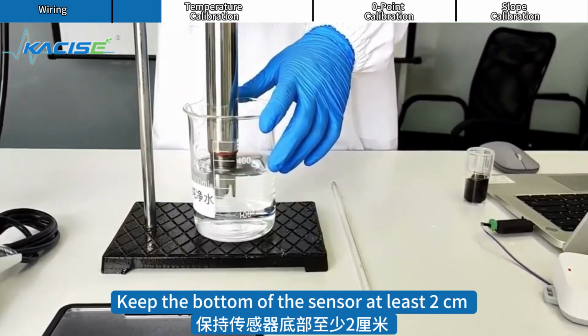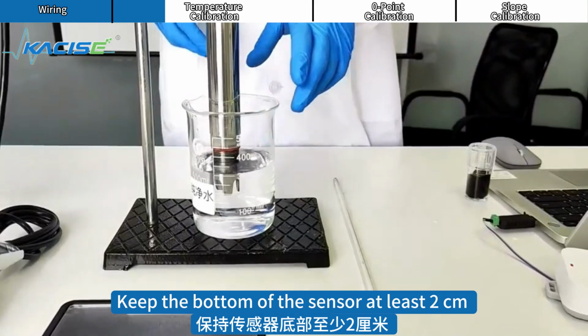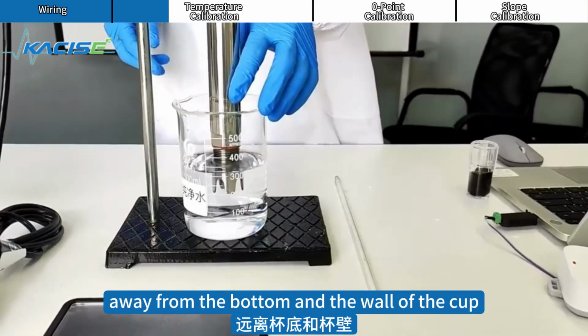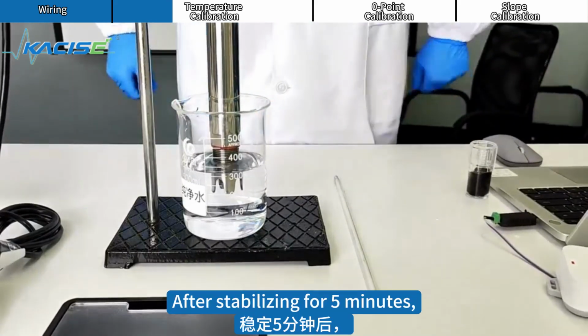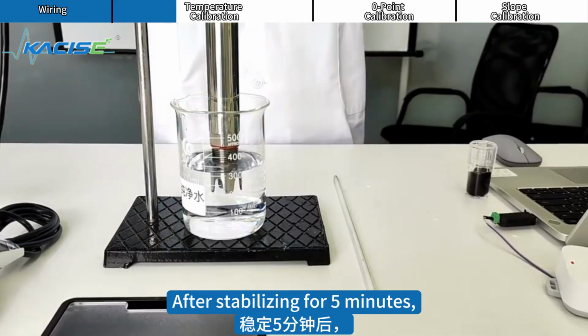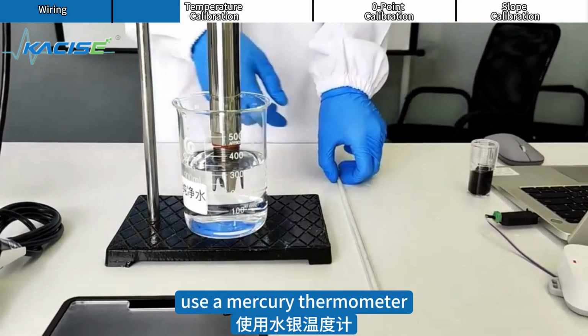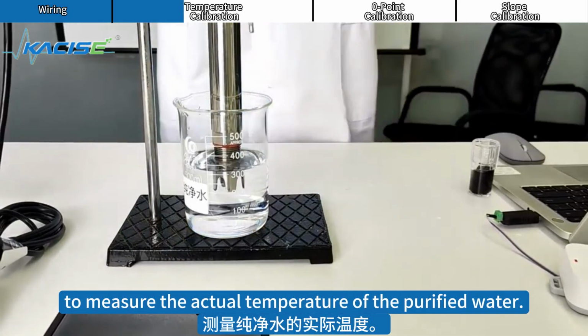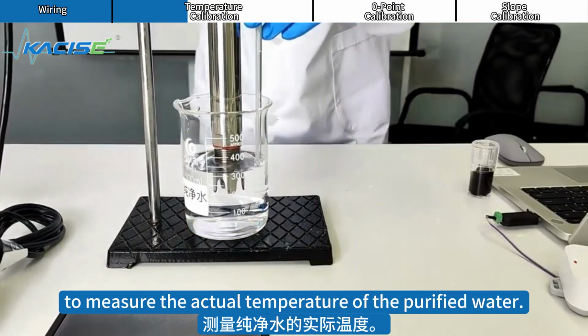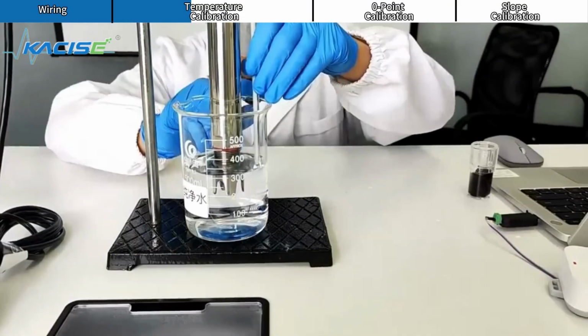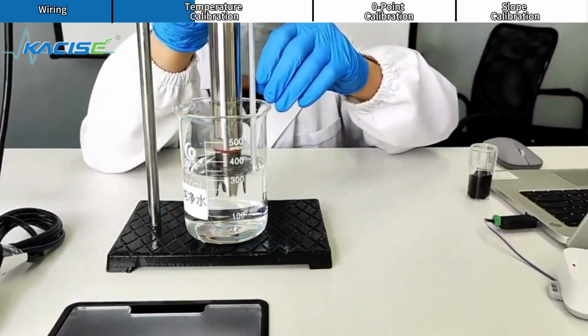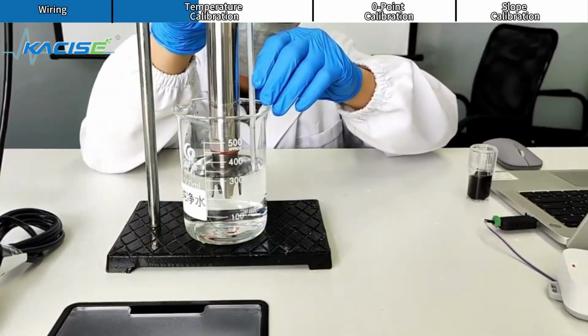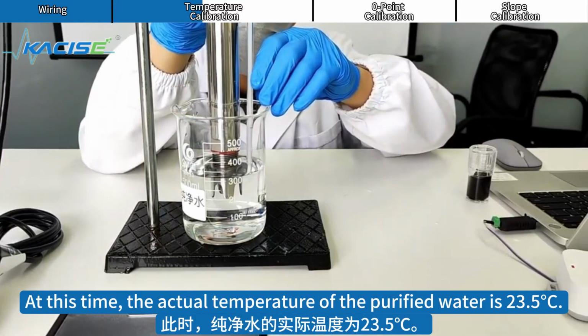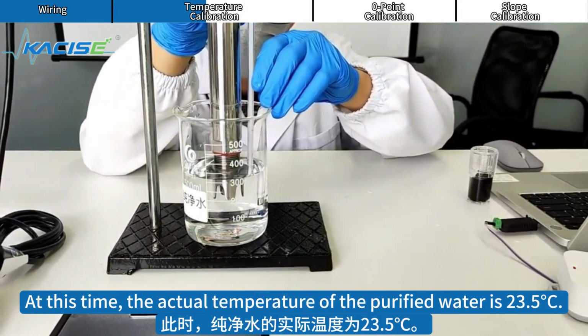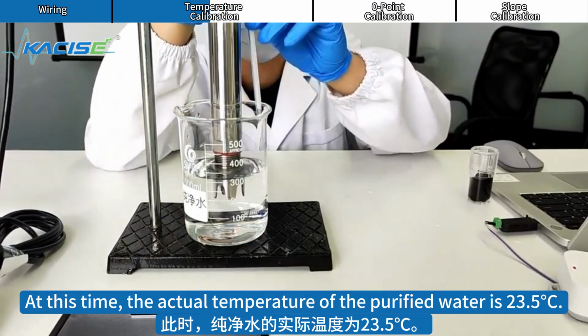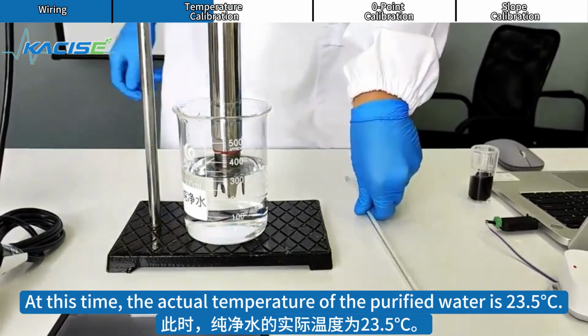Keep the bottom of the sensor at least 2 centimeters away from the bottom and the wall of the cup. After stabilizing for 5 minutes, use a mercury thermometer to measure the actual temperature of the purified water. At this time, the actual temperature of the purified water is 23.5 degrees Celsius.